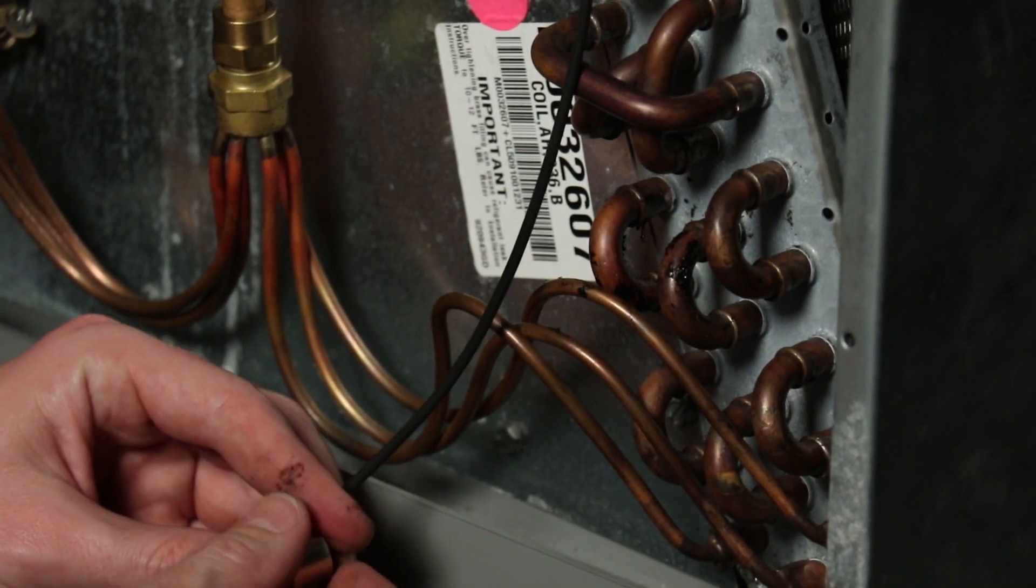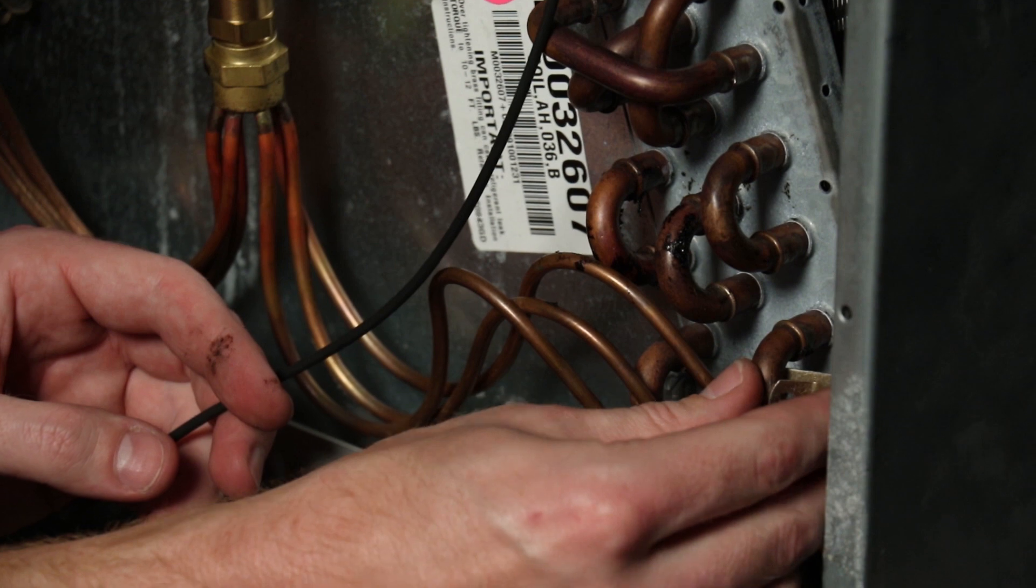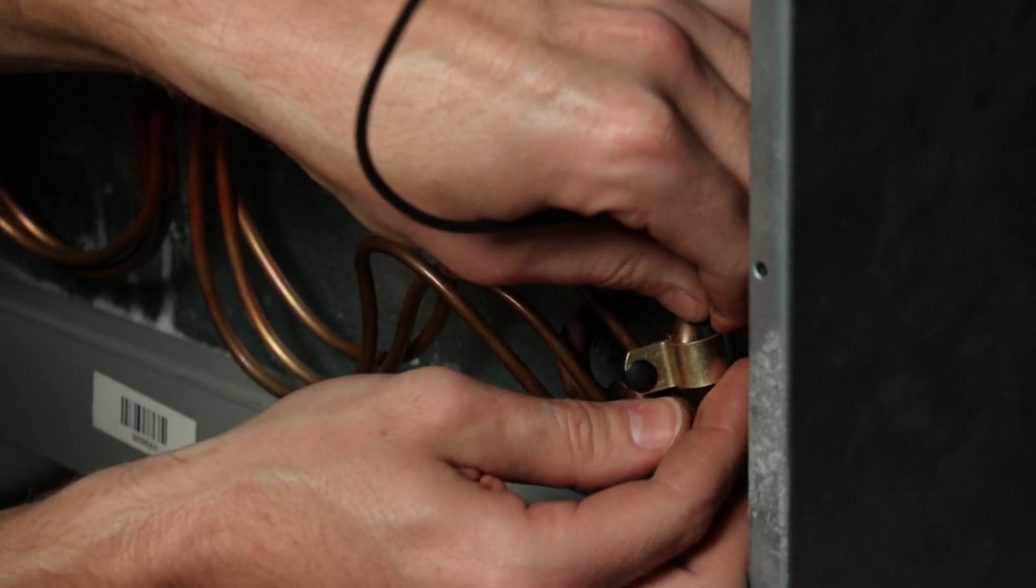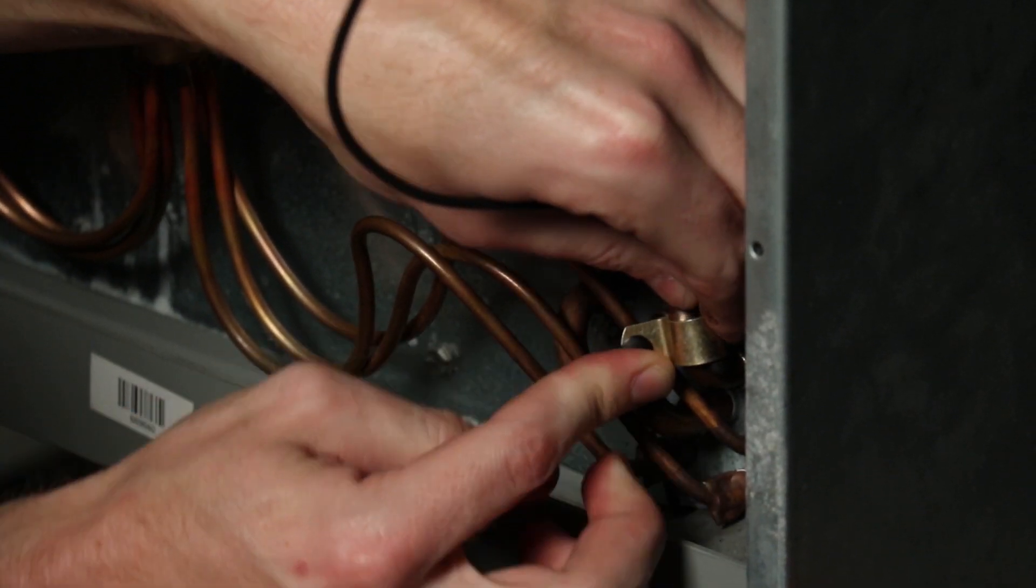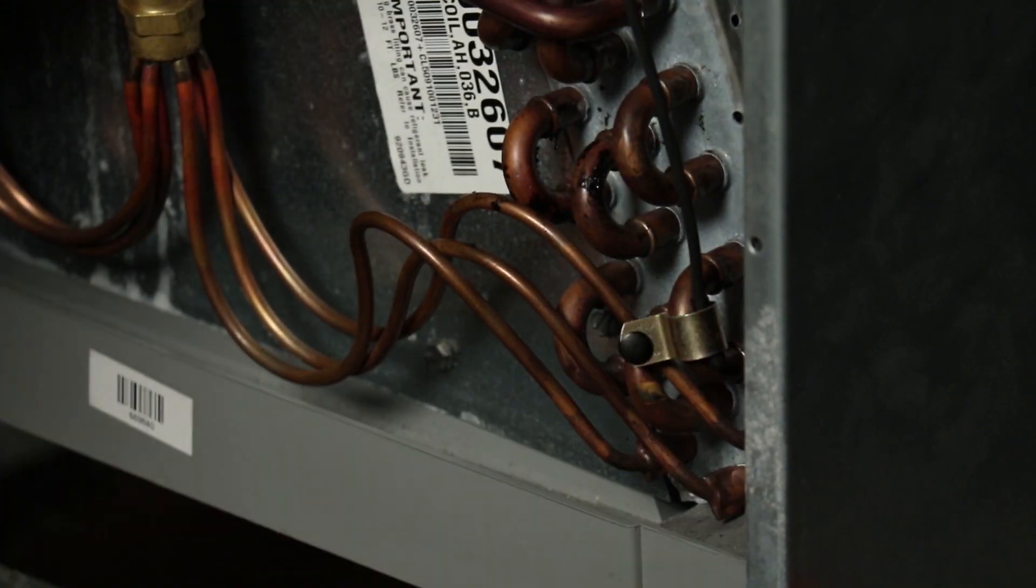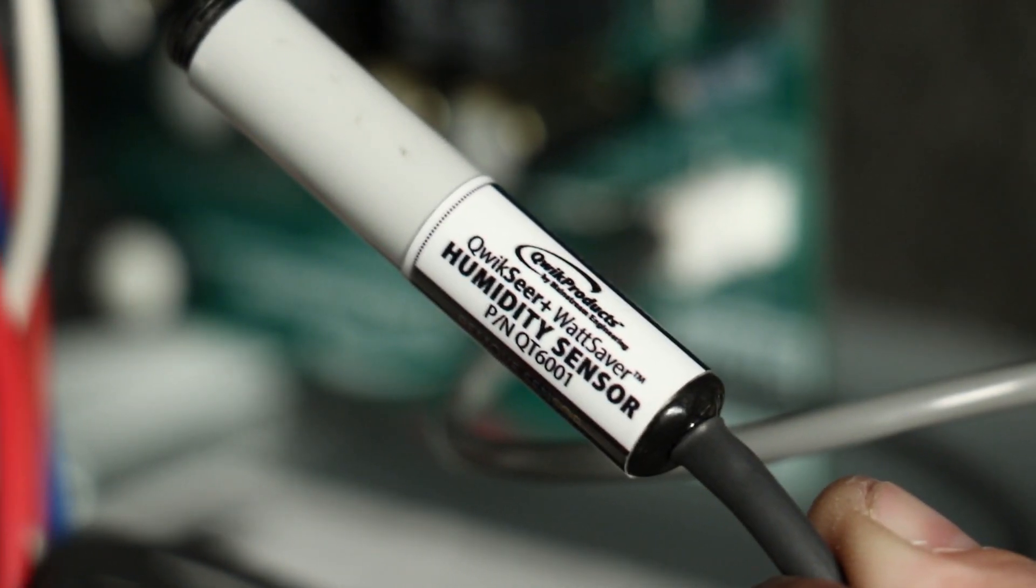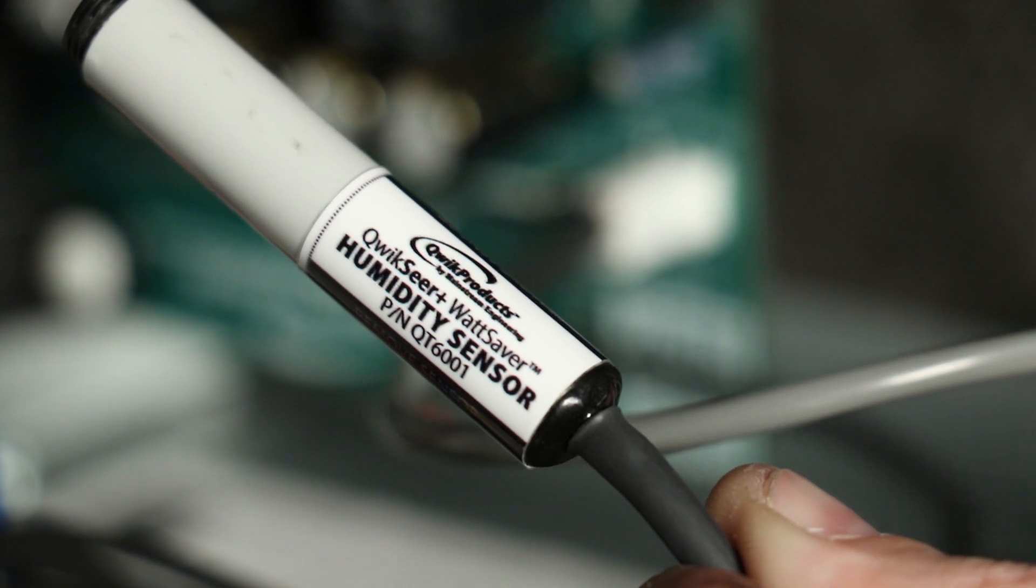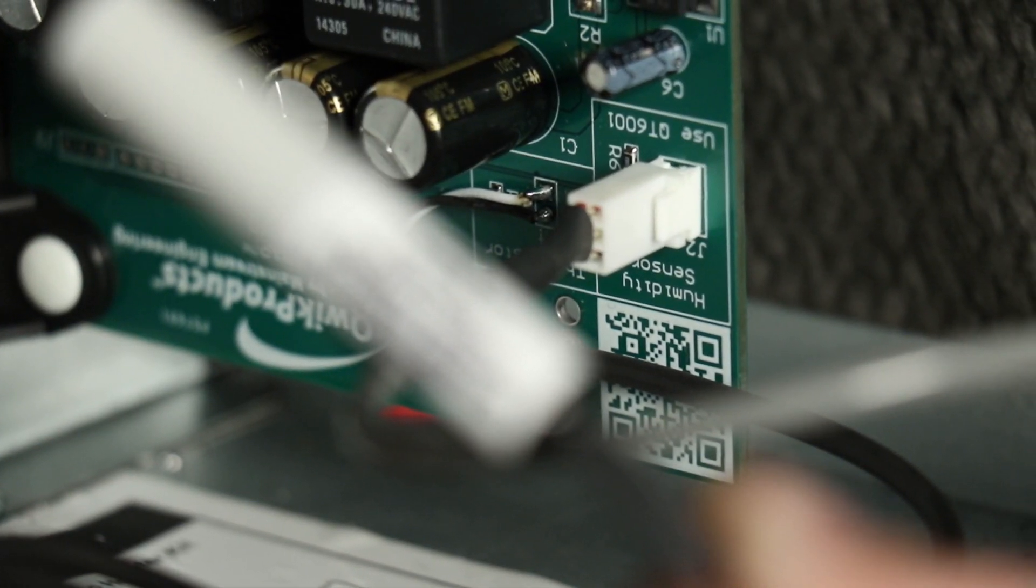Step ten is to route the thermistor from the quick swap board down to the evaporator coil. The thermistor must be installed on any return bend near the coil inlet using the loop clamp provided. If the optional humidity sensor is to be used, install it now following the instructions that it comes with.